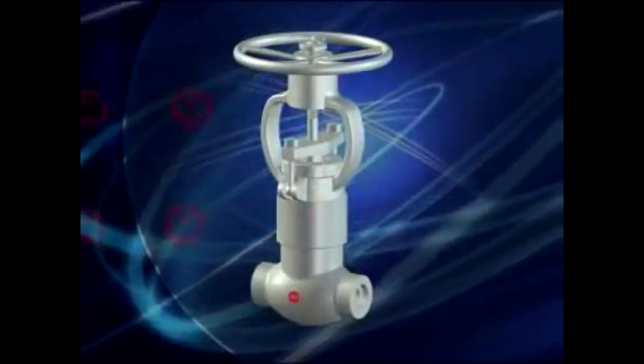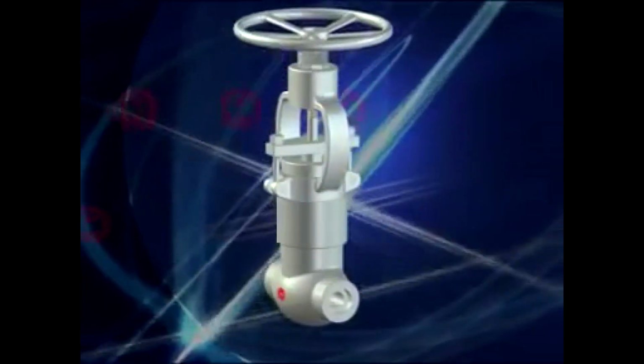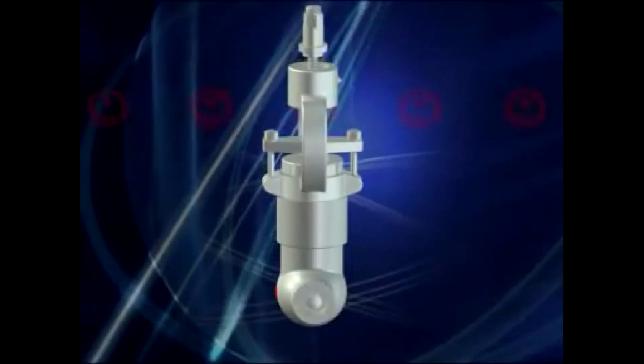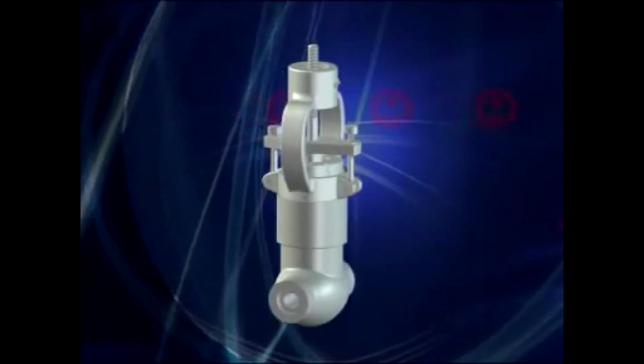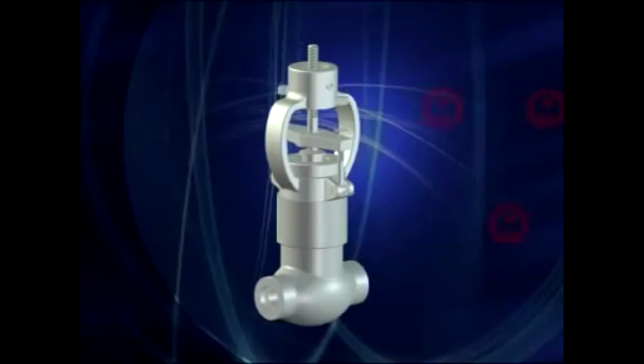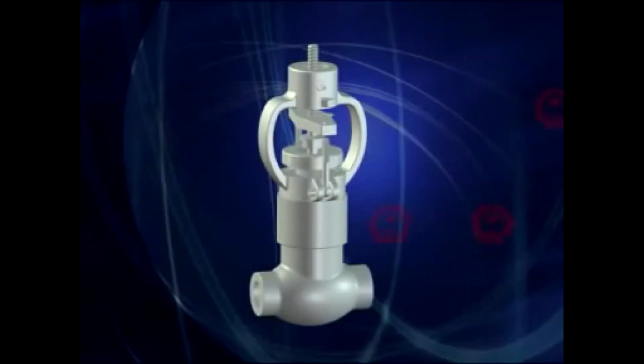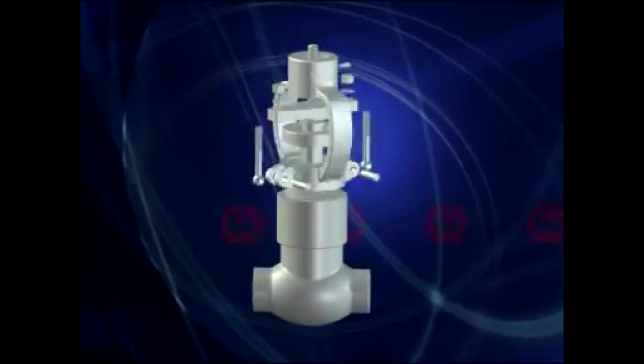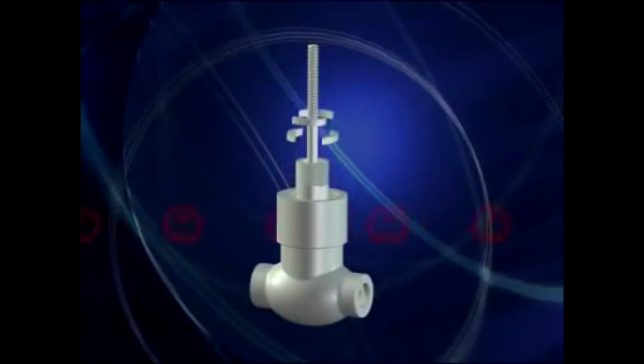The valve cover and the medium pressure press the seal ring. Simultaneously, the medium pressure presses the charging ring along the valve stem, thus achieving the effect of double self-tightening sealing. Fourth, the direction that medium flows is without any limits, easy to install.